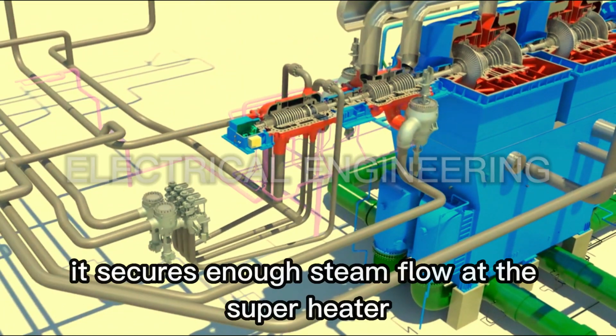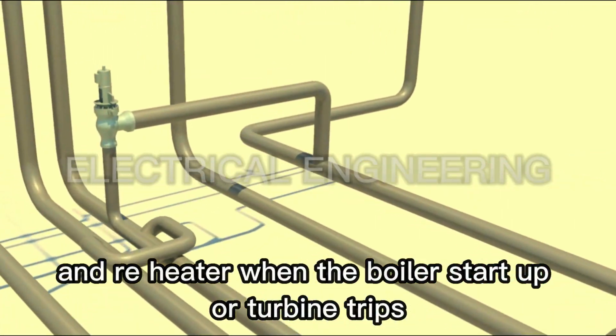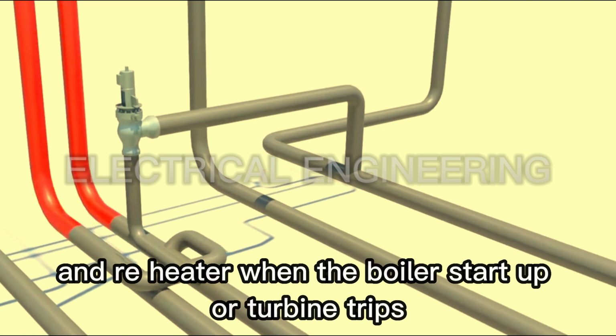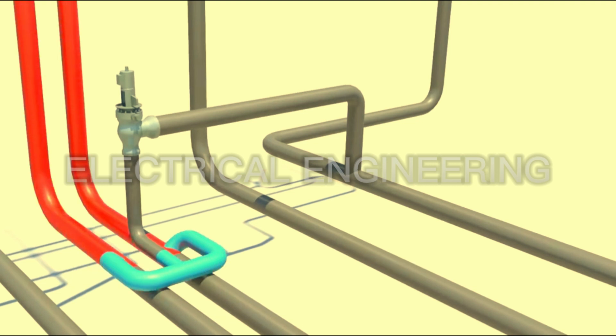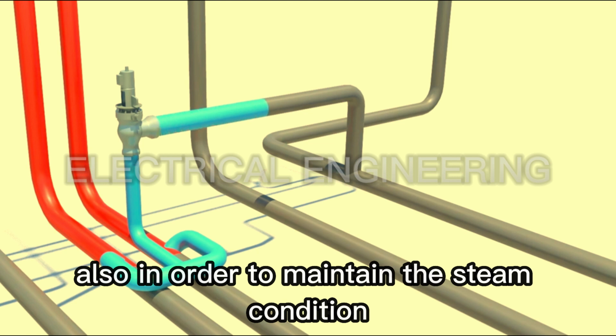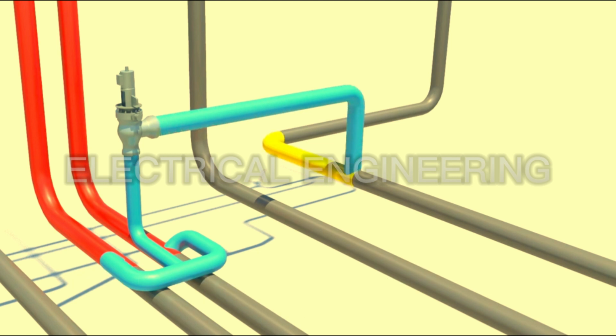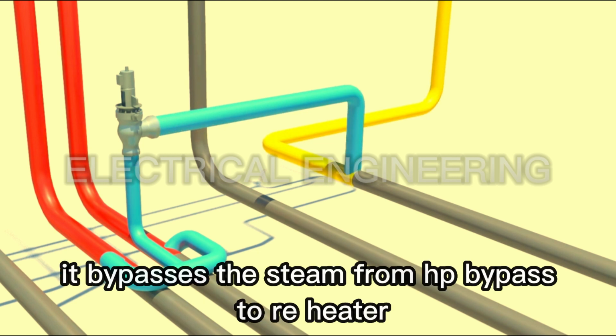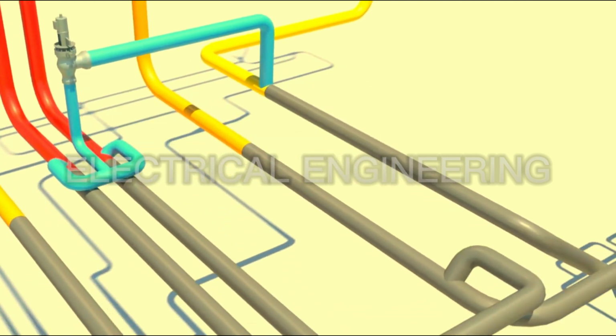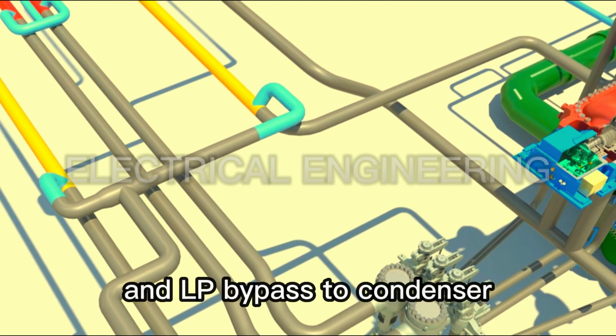It secures enough steam flow at the superheater when the boiler starts up or the turbine trips. Also, in order to maintain the steam at a high quality, it bypasses the steam from the HP bypass to the reheater and the LP bypass to the condenser.